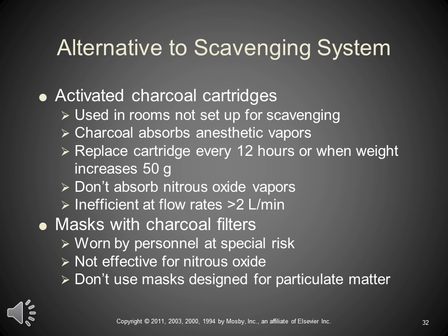I'm not a big fan of activated charcoal cartridges, not because they don't work, but because people don't use them properly. They hook one up and think it's good for the life of the anesthesia machine. And 20 years later, they're still using the same activated charcoal filter, which is no longer viable or functional.